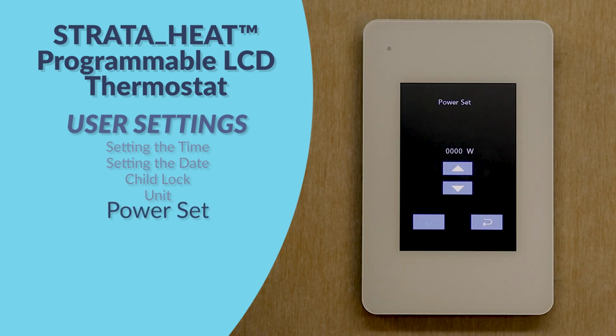The power set function is designed to allow users to input the total wattage of the underfloor heating wire being used. This information can be found in the manual and other materials associated with the thermostat wire. By inputting this number, the unit will provide an estimate of the total kilowatt hours the system has used over time. This, with the knowledge of the user's local utility rate, can provide an estimate of in-service operating costs of the system. Total kilowatt hours can be viewed in the energy use function of the thermostat.